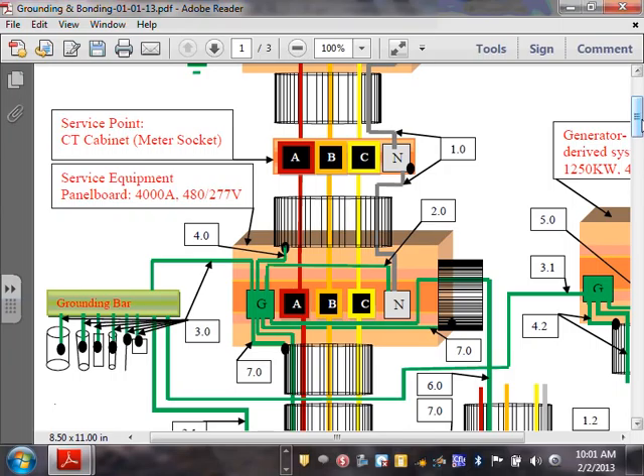They got rid of it actually in 2011. It has to be equipment grounding conductor, grounding electrode conductor, main bonding jumper, system bonding jumper, supply side bonding jumper. All this terminology, you have to use the right terminology so you can find them in the code. So this one here is the grounding electrode conductor. We take it into the bar. We're not talking about the sizing yet.